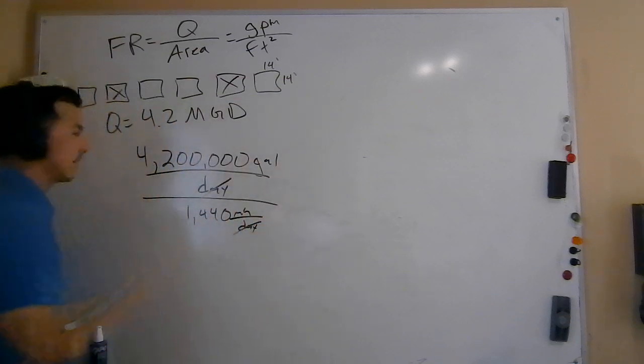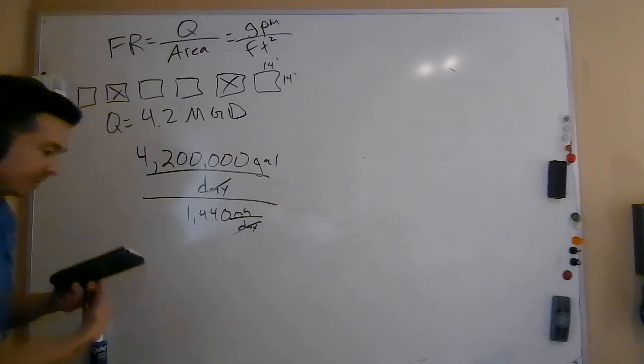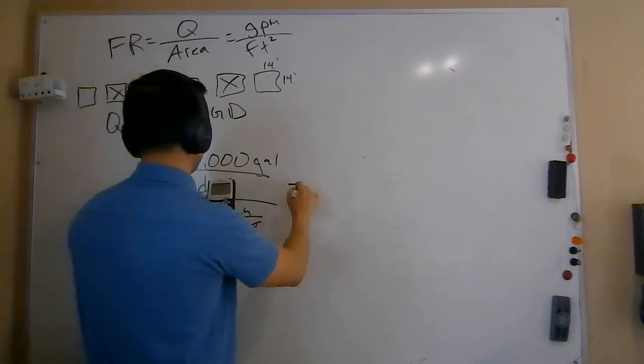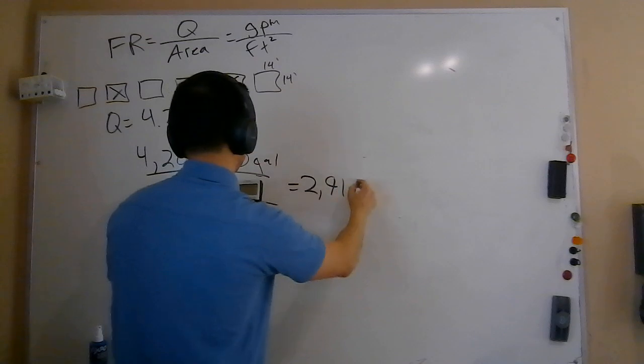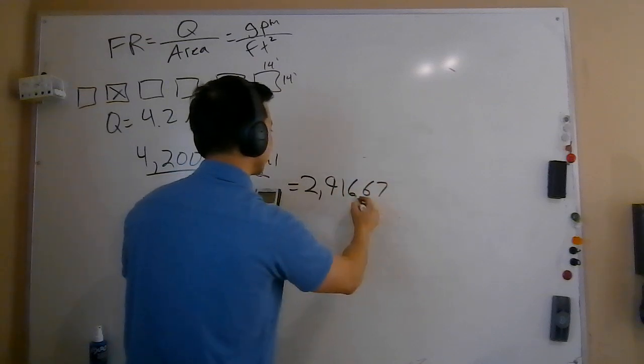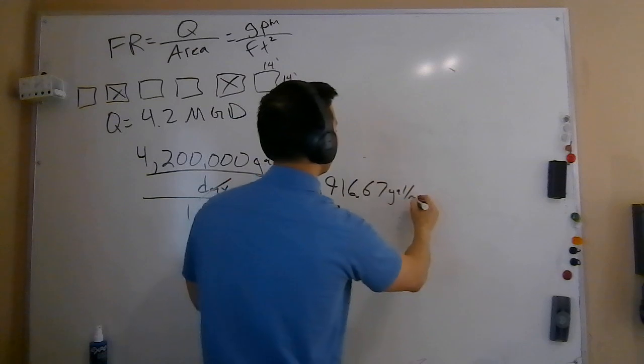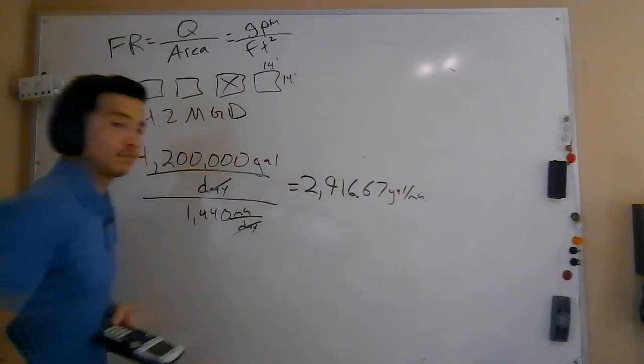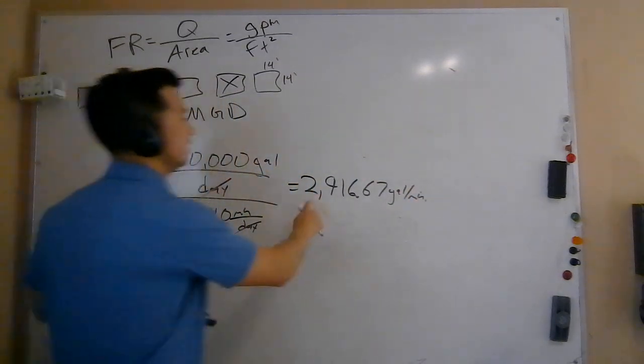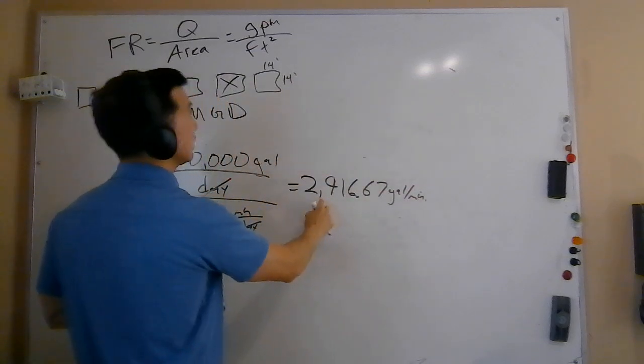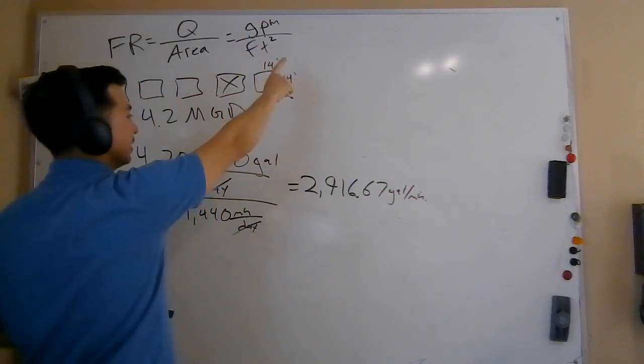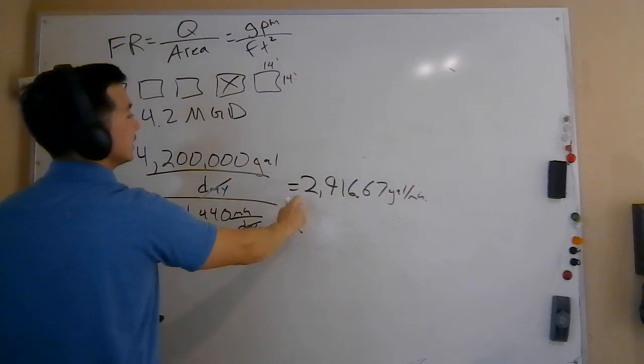This is going to allow me to cancel out my days. So I'm going to take this 4.2 million number, 4,200,000 divided by 1,440. And that's going to get me to a flow rate of 2,916.67 gallons per minute. Now I'm just going to leave this number in my calculator for the sake of ease, but this now becomes my flow rate. And this is what I need in GPM.